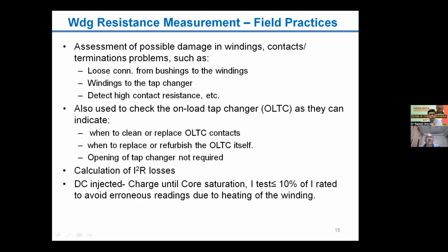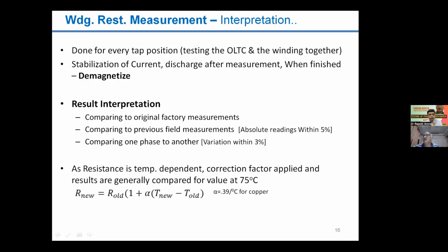For this test, DC is injected, and if the current is taken to the saturated value, core saturation takes place, but normally the test is performed below 10% of the rated current to avoid erroneous readings due to heating of the winding. Okay, next. This test is done again on every tap position, testing the OLTC and winding together, keeping them in circuit.